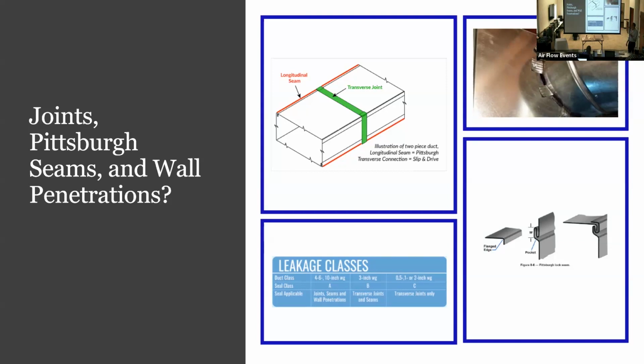But even this one, again, this is a bad one, it's just for example, but this doesn't need to be sealed. So you cut a hole in the side of the ductwork, you put a tap on it. Theoretically, you think that that's going to leak, but it doesn't need to be sealed once it's low pressure ductwork, where all your little takeoffs and fittings and all that stuff is. So again, SMACNA says this is cool, that's what you get.